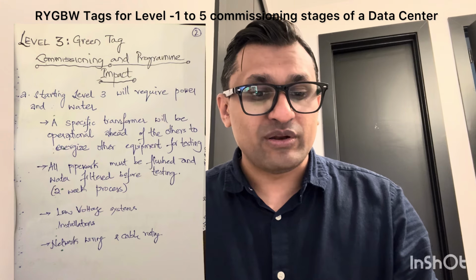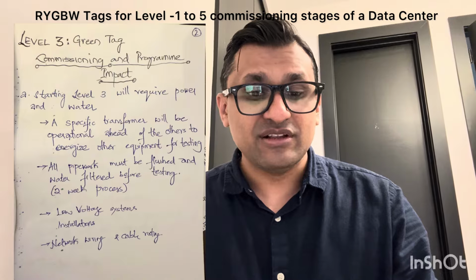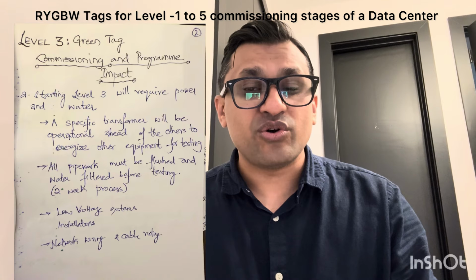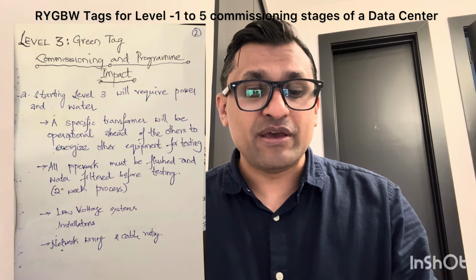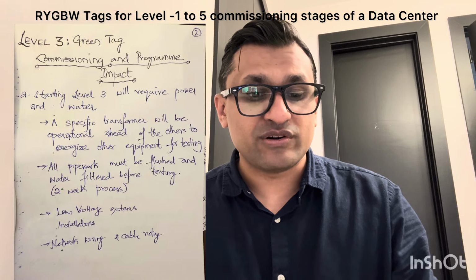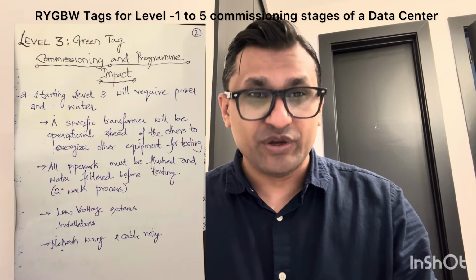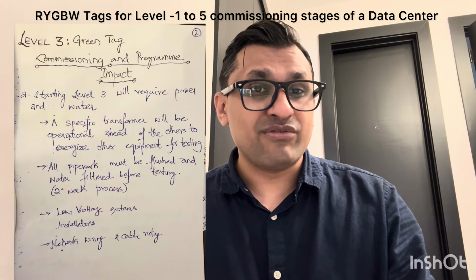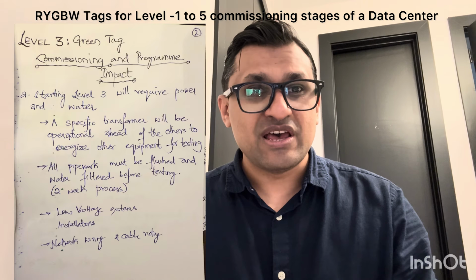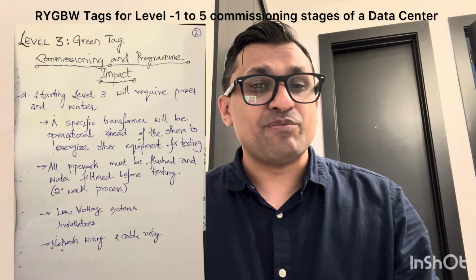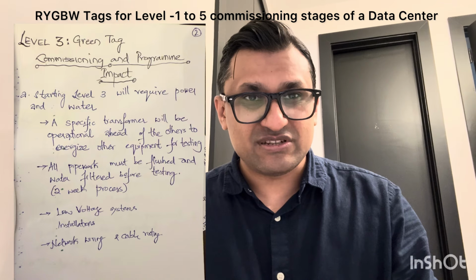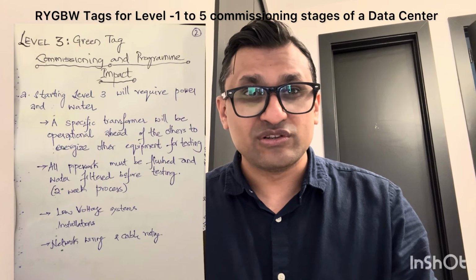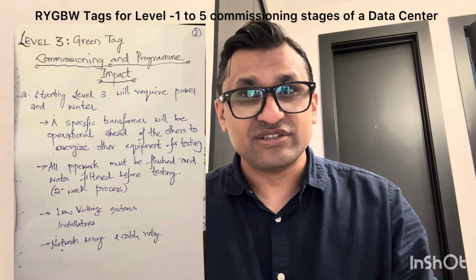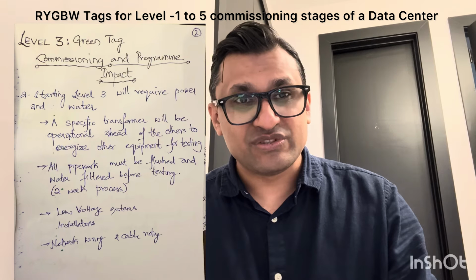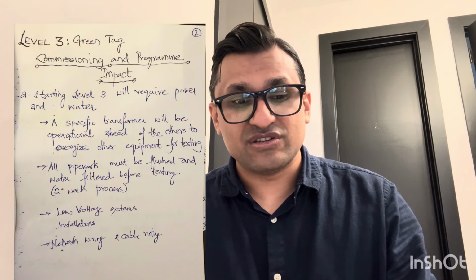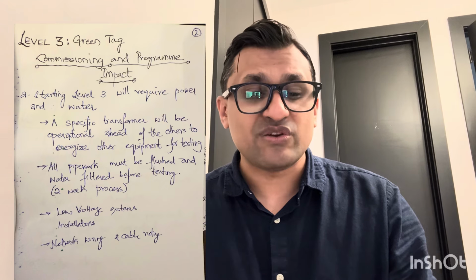Specific transformers will be operational ahead of the others to energize other equipment for testing. All pipe work must be flushed and water filtered before testing. It's a 2-week process approximately. We need the pipe work because if we are using chilled water systems, any kind of hydronic systems, the pipe work must be flushed because there could be impurities, debris. You don't want any clogs, you don't want any loss of heat transfer, any losses or problems in the water system. So all pipe work must be flushed and water filtered.